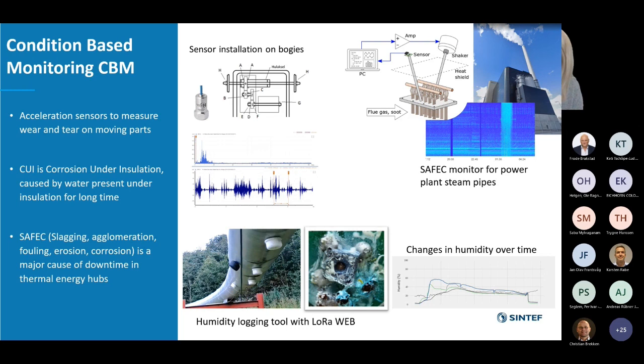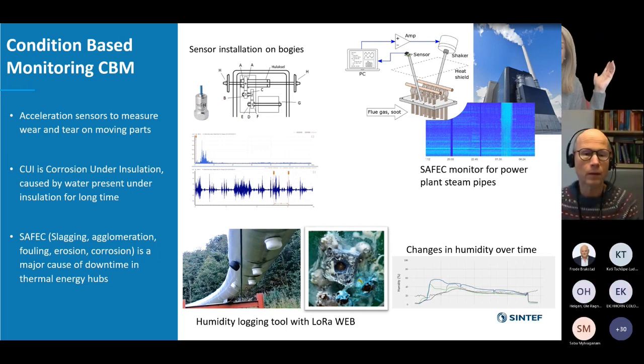It involved a mechanical design where we actually created the sound—instead of installing stuff along the pipes, we started banging the pipes to make a different sound. The more the scaling, the different the sound, and we measure that. Designing the geometry of the shaker and detector, their relative position, and picking out the frequencies had to be simulated and tested, then we built the electronics around it to measure it. That's something we're progressing, and we've submitted an EU project proposal on this as well.